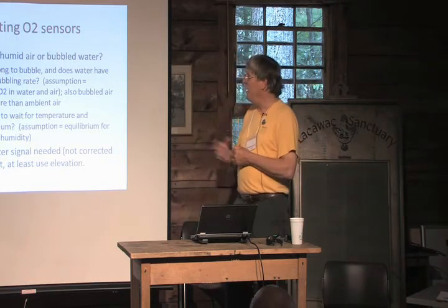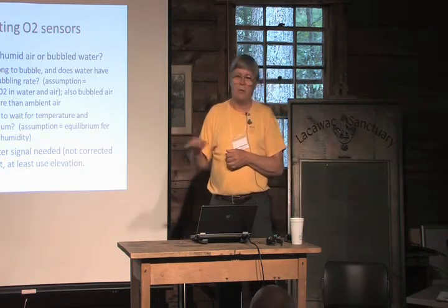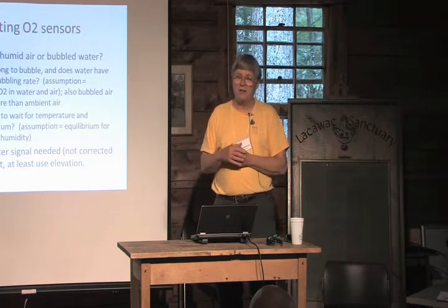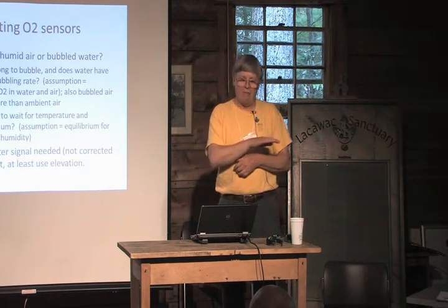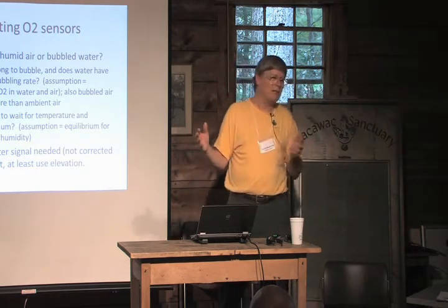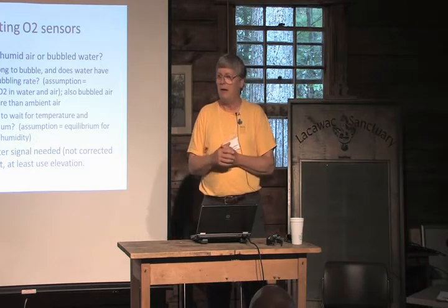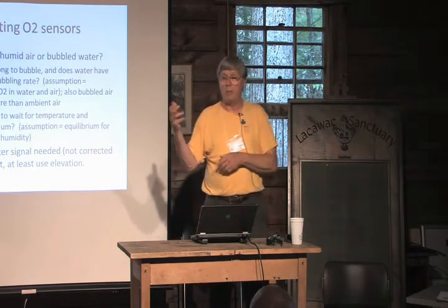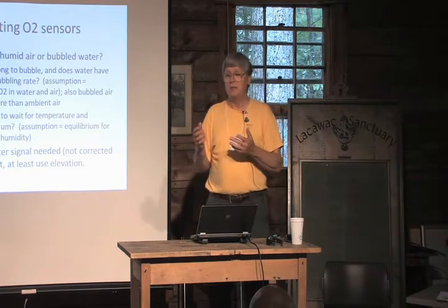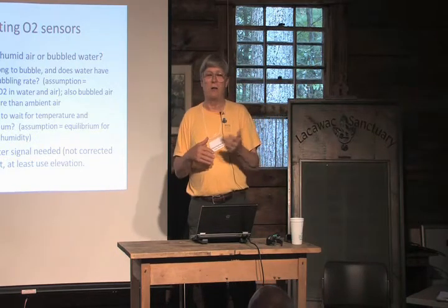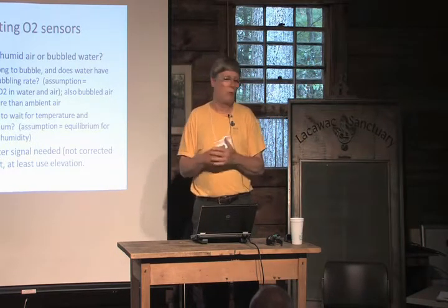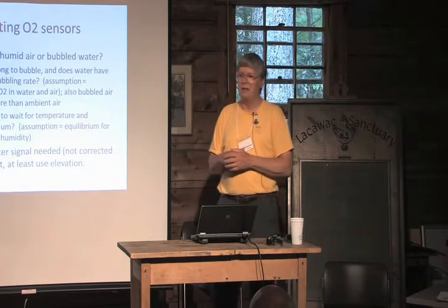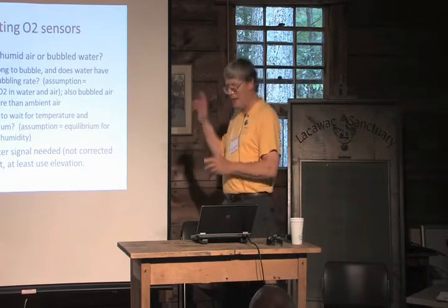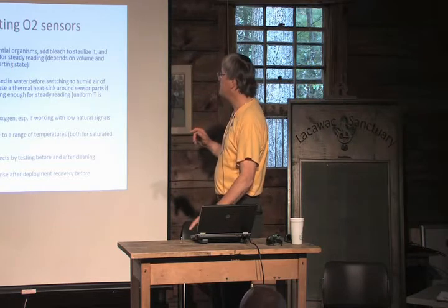I prefer a continuous recording of barometric pressure, because then you can have a continuous recording from your electrode while it's in the calibration chamber and you can correct for it, but a single handheld barometer might do. But what you must avoid is barometers from a weather station that are corrected to sea level, because that's the standard for weather, to correct the barometer to sea level. You don't want that. You want the real pressure at the point where you're making your measurement.